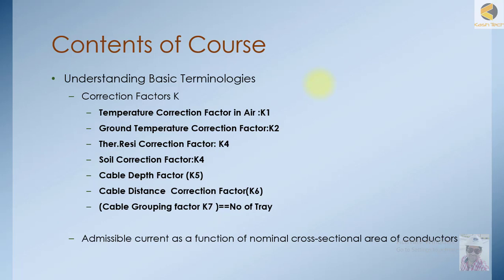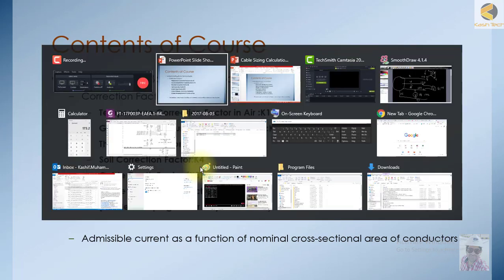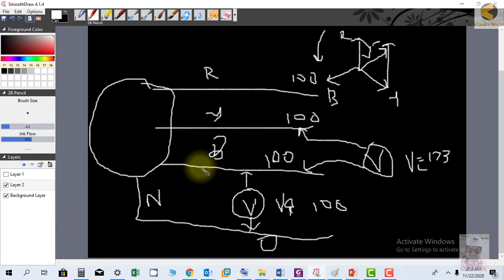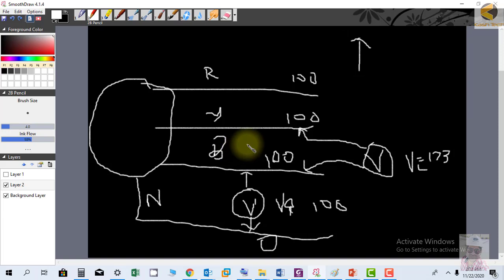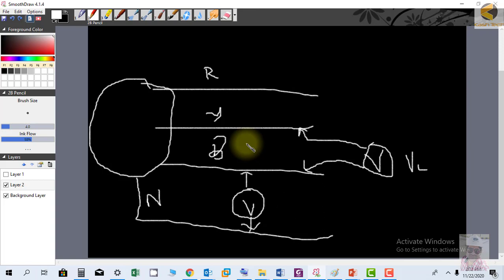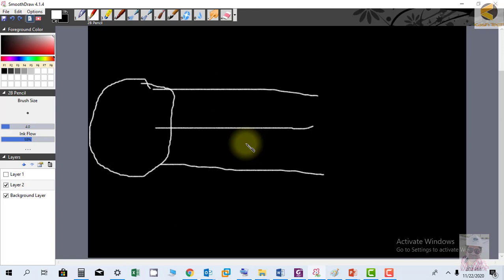If the cable is running alone, the correction factor K could be 1. But if the cable is used with 10 other cables together in a very tight conduit, there will already be a heating effect. You then have to multiply by a certain factor called the K factor. You cannot use the cable at its full capacity because of certain environmental factors. All these factors are called K factors.